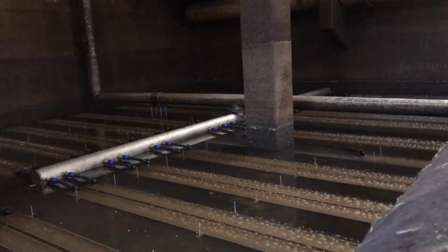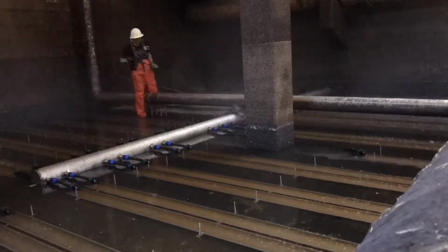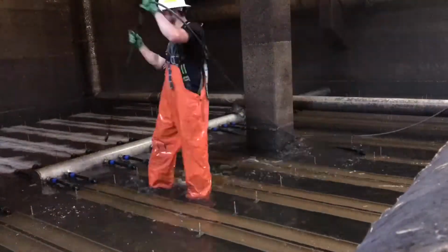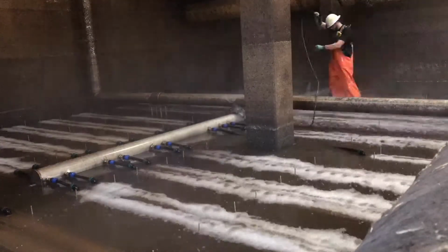So just as we suspected, there's a good amount of fouling on portions of this air leg. Now we'll get down there and we'll get it washed off, and then we'll see what we've got for flow. So the trick to getting these diffusers to run correctly is consistency. Now that's consistency in the speed we move the pressure washer, and consistency in the distance the pressure washer is from the membrane. You can imagine if I'm looking for an even flow out of all the panels, it'd be odd if I did a lot of pressure washing on one panel and only a little bit on another.